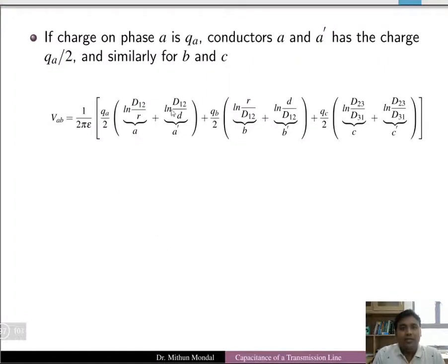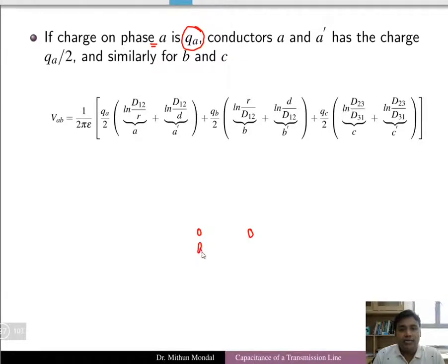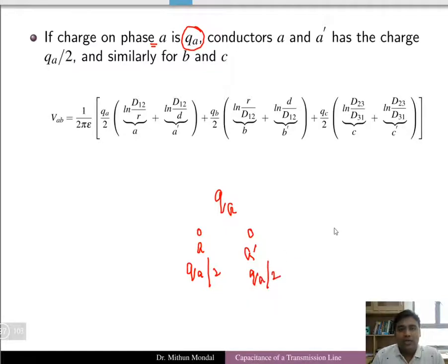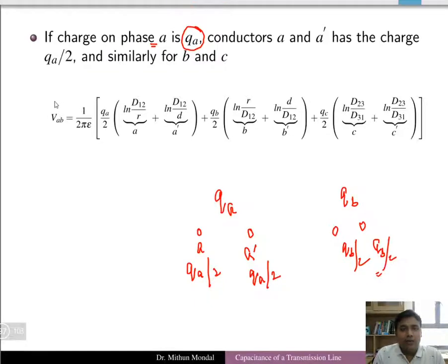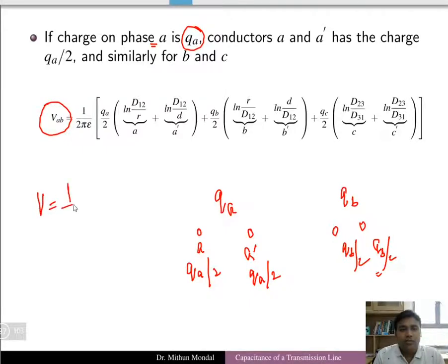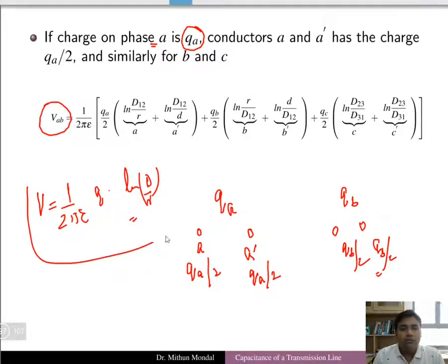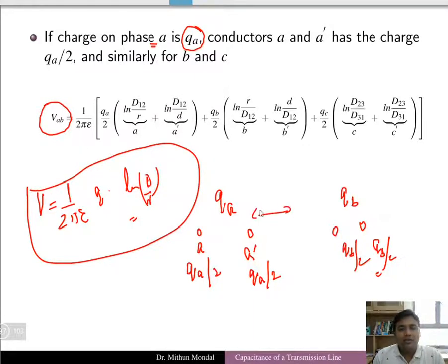If the charge on phase A is QA and there are two conductors in that phase, conductor A carries QA/2 and conductor A' carries QA/2. Similarly, phase B carries QB/2 each, and the same applies for phase C. The general formula for voltage is (1/2πε) × Q × ln(D/r), and we will apply this fundamental formula to the bundle conductor configuration.